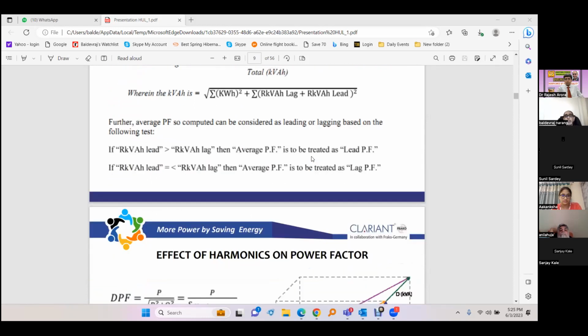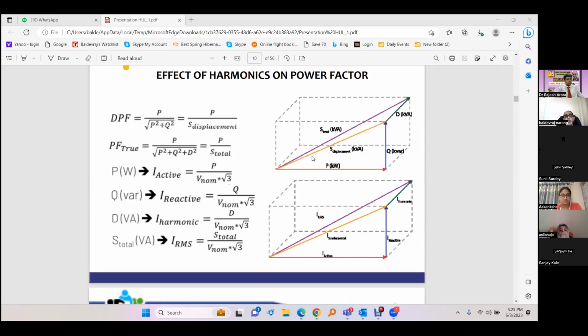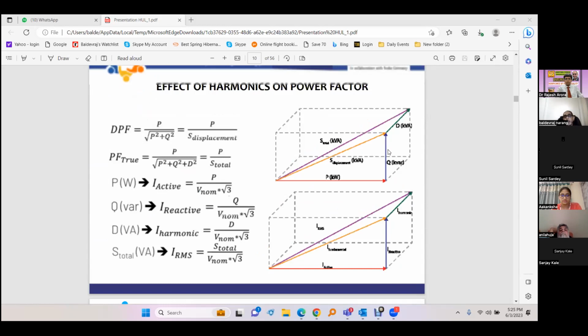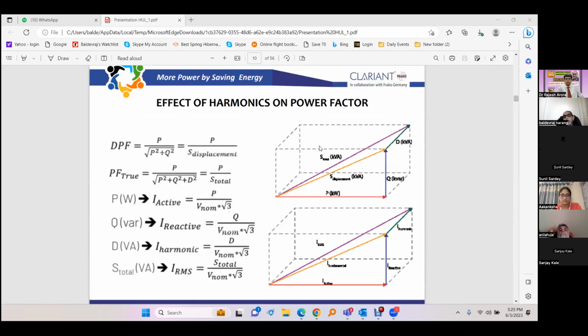Now harmonics have added another angle to the power factor. There is a distortion. Instead of a two-dimensional vector diagram, we have a three-dimensional one, and the third dimension is a deviation due to harmonics. If that is also taken into account, we have the true kVAH and the true power factor, and everything changes. This impact is there on the billing. So far, I don't think the electricity boards have started using this distortion power factor for calculating the actual kVAH, but maybe they will start sometime or other if this becomes a problem.